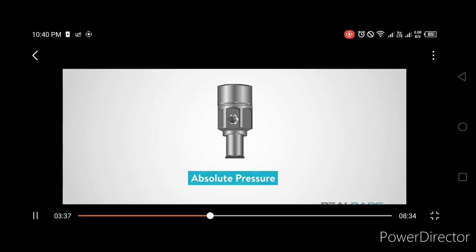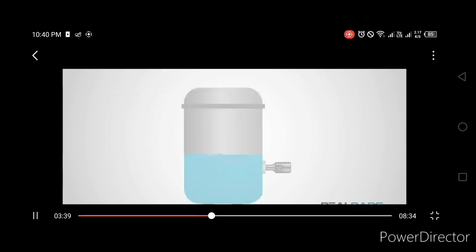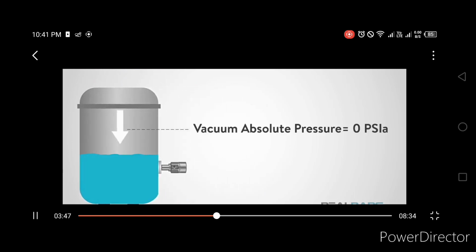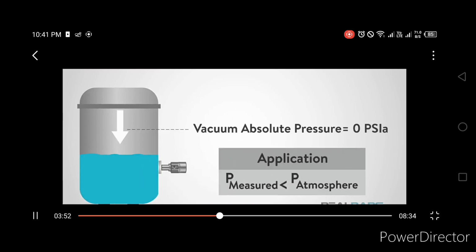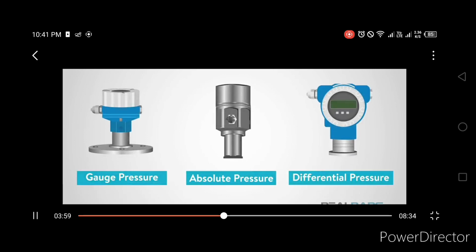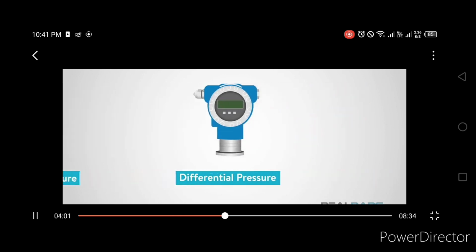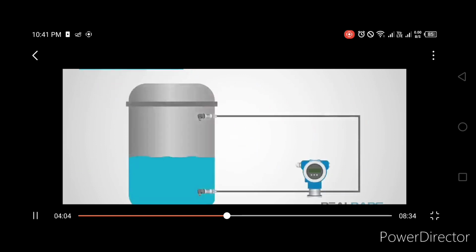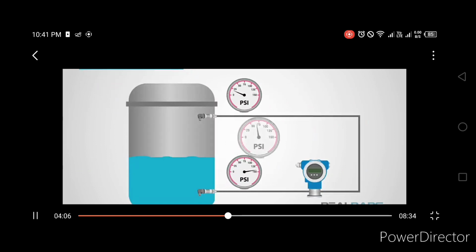The next type is absolute pressure. Simply put, this is the pressure as measured against absolute vacuum. A full vacuum will have an absolute pressure of 0 psia and increase from there. If you need to read a pressure that is lower than atmospheric pressure, this is the type of sensor you would use. The last type that is commonly monitored in the industry is differential pressure. This is exactly what it sounds like: the difference between two pressures, a pressure being measured and a reference pressure.